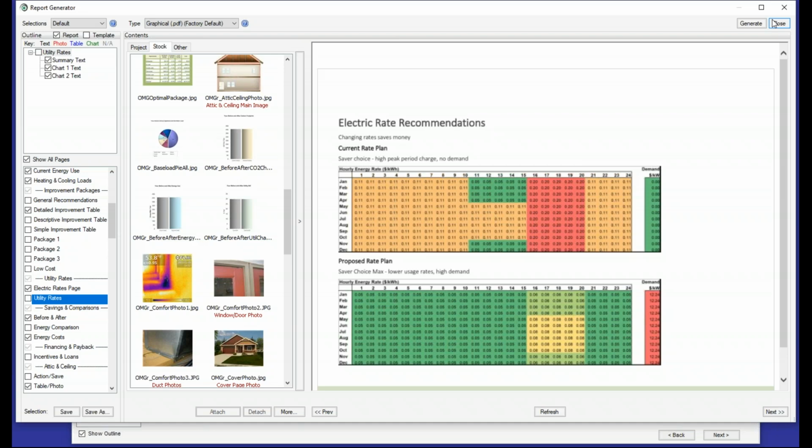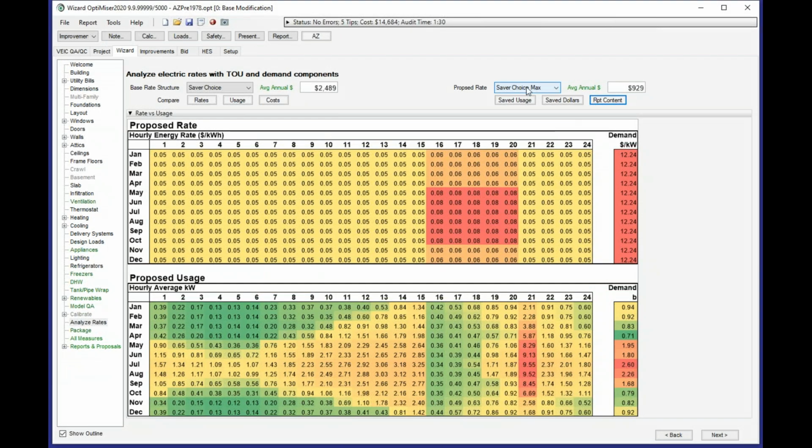The relative difference caused by the measures, I think, is still a good estimate. But in order to make the total demand charges align more closely with what your users are actually seeing on their bills, we're going to need that step of having an import of the true hourly data, and then tuning the model to that. So for now, this is just based on the hourly model results and the rate that you've chosen. So the demand charge is there in the rate.